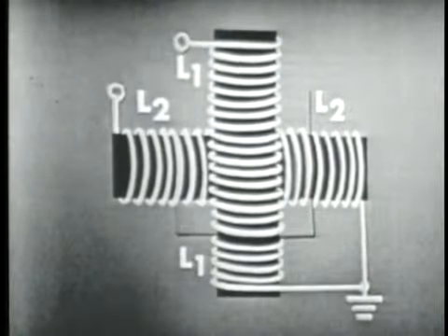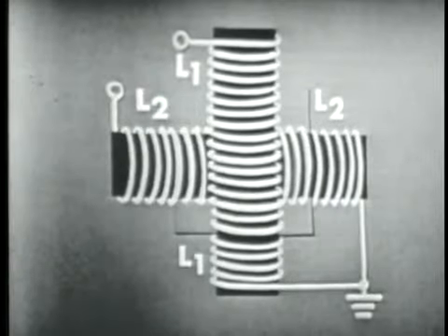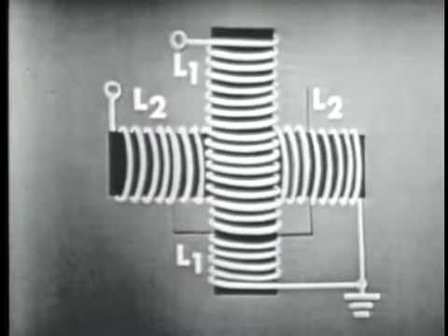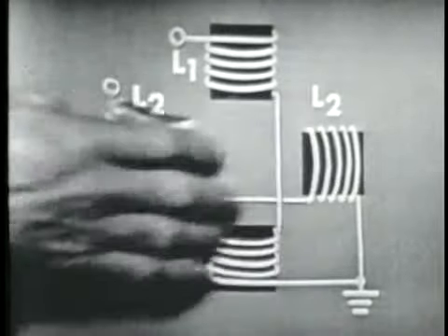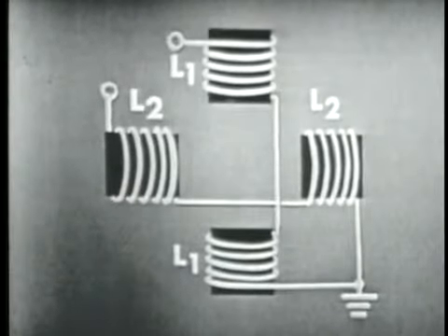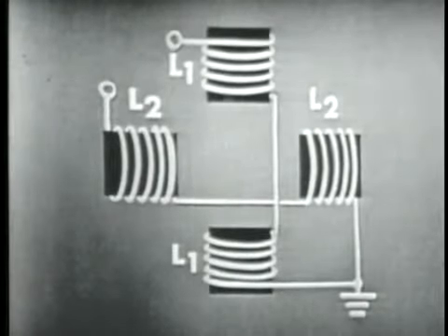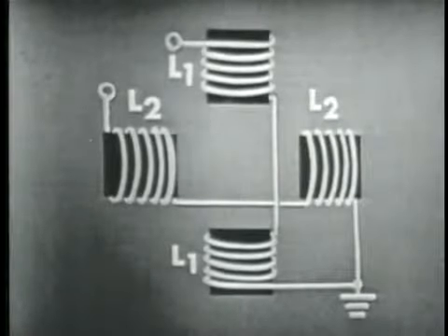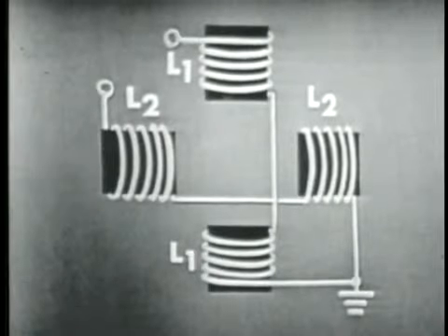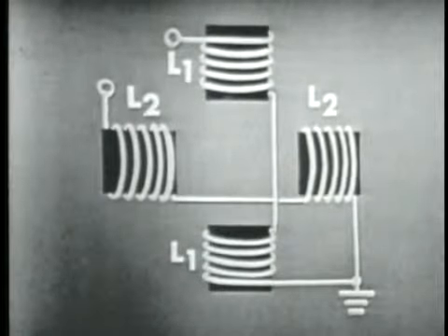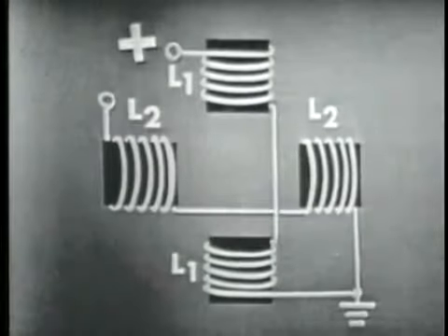Now, actually, there are really only two coils. We'll call them L1 and L2. Now, L1 was wound something like you see it, and then the core was cut in the middle and stretched apart. Now, it's still one coil, but now it's got a gap in the middle. L2, the other coil, was constructed in the same way. Now, L2 will supply a horizontal magnetic field, and L1 will supply a vertical magnetic field. So if we supply voltage to just L1, we'll, of course, cause a vertical magnetic field. Like this. And the field lines up like this.